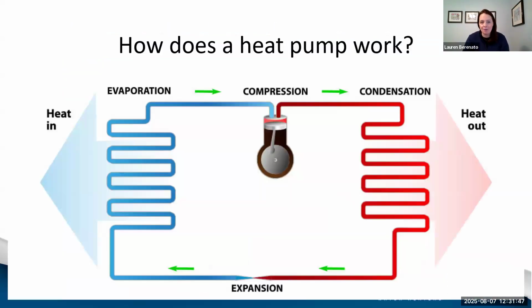So how exactly does a heat pump work? This is a very simple image, but it basically shows you how the heat absorption, or evaporation, occurs. That's the heat pump pulling heat from the surrounding air using refrigerant that absorbs its thermal energy. And this will happen with cool air as well, not just warm air. Then you have your heat compression. That's where the refrigerant is compressed, increasing its temperature significantly as it moves throughout your system. And last, we have the heat transfer, or condensation. That is a high temperature refrigerant, which transfers heat to the water in the tank through a coil or a heat exchanger, efficiently heating your water.